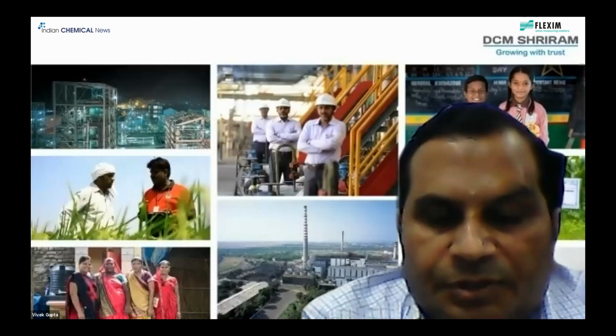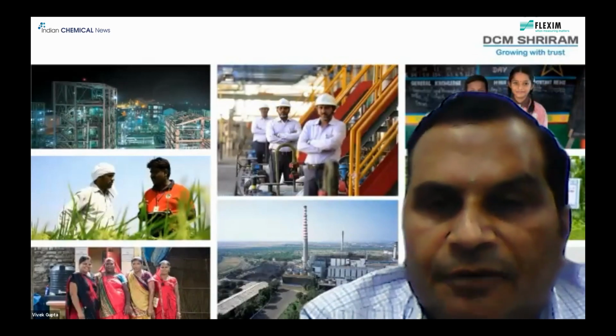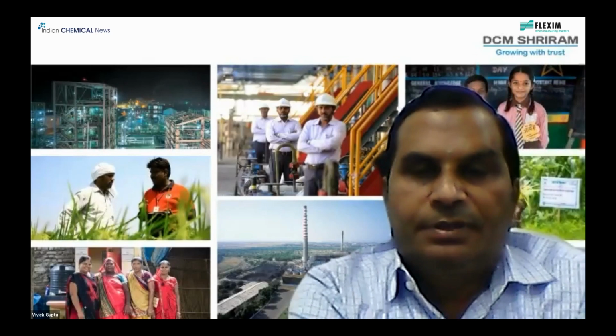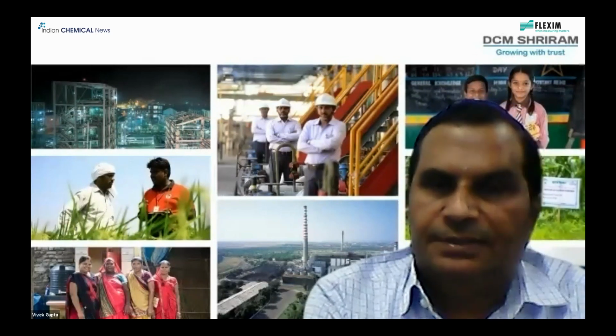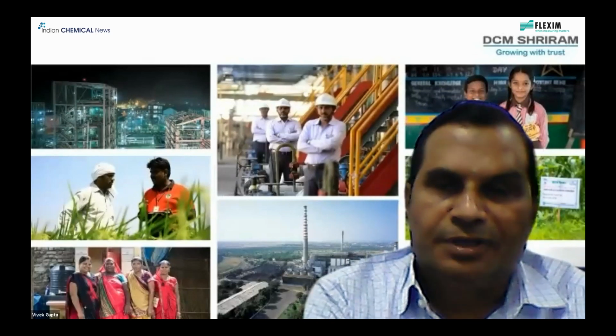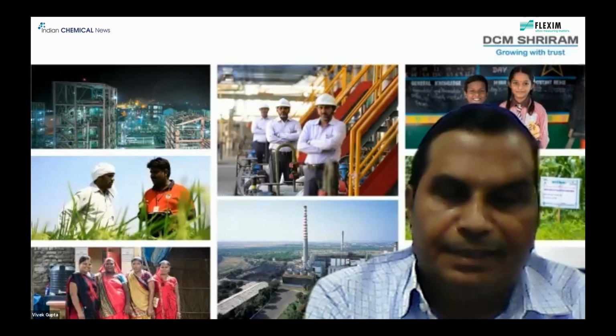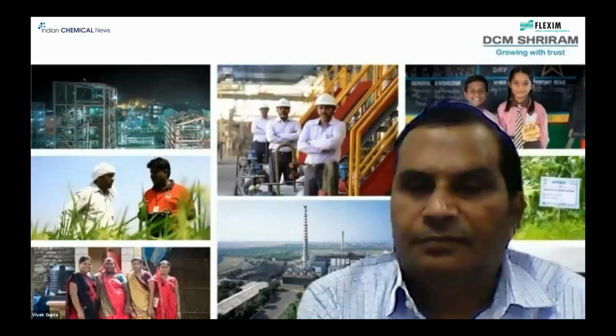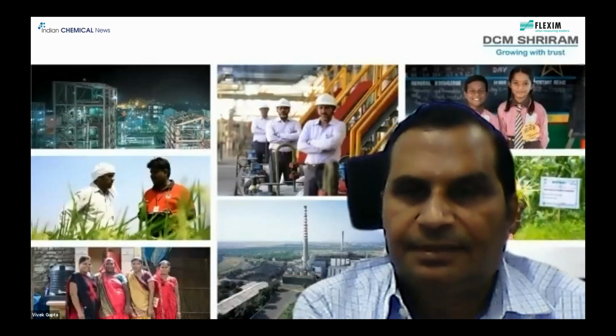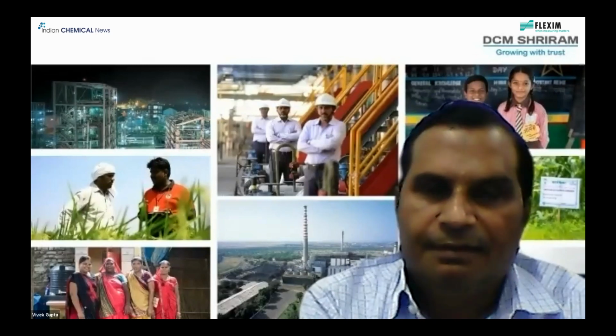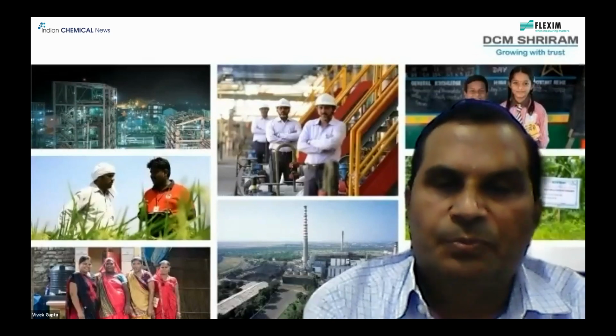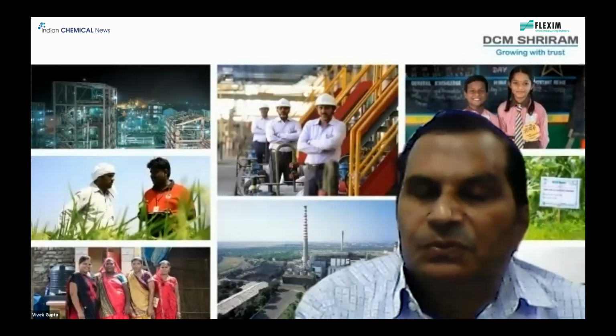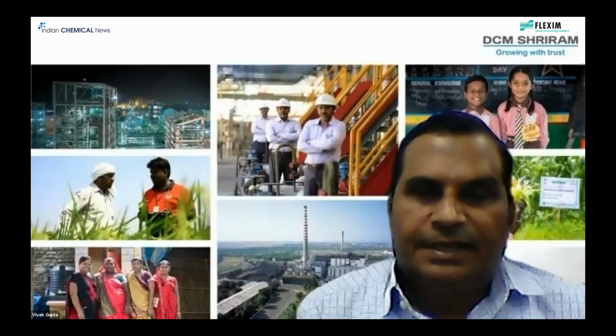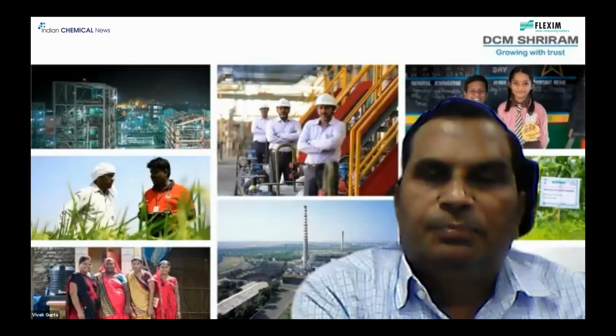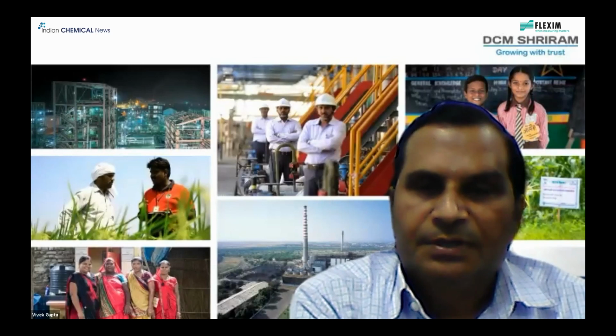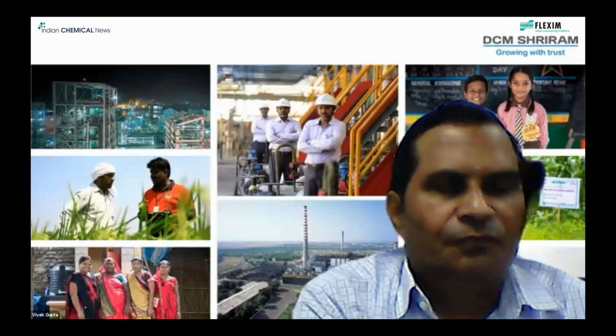Yeah, Praveen, at DCM Shriram, as I was explaining previously, we had installed one clamp-on type flow meter in the cooling water line in our 66 megawatt power plant, and that was a very big carbon steel line of 1800 mm and 10 mm thickness. Instead of going for a different type of measurement, we installed it in January 2020, and till date it's working satisfactorily, except that where you put a sensor outside the pipe, you sometimes have to use coupling fluid if there is any variation in the flow measurements or the plant reports that the readings are not looking good. We did that also after 14 or 15 months.